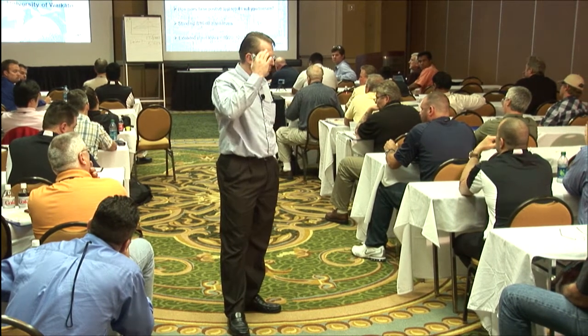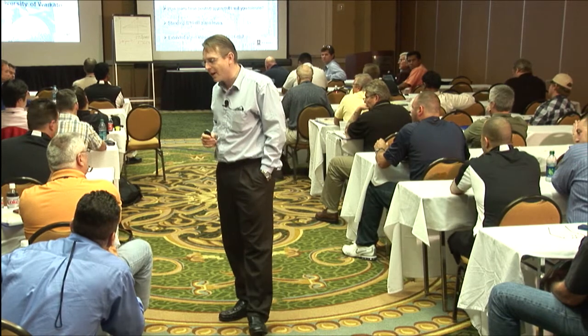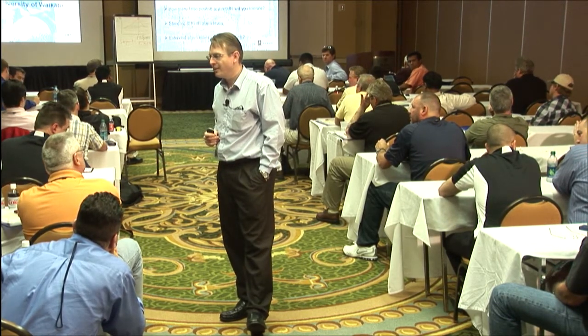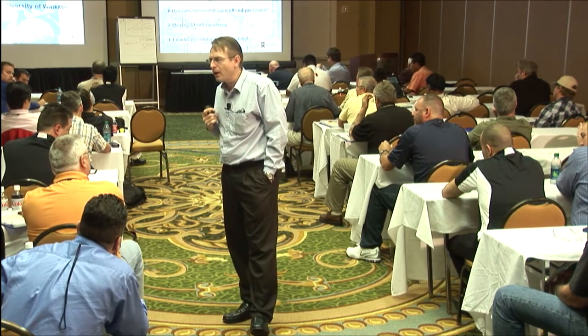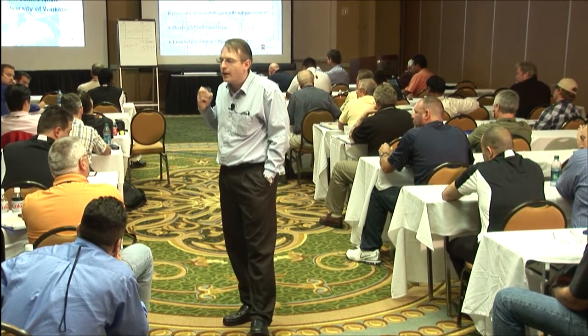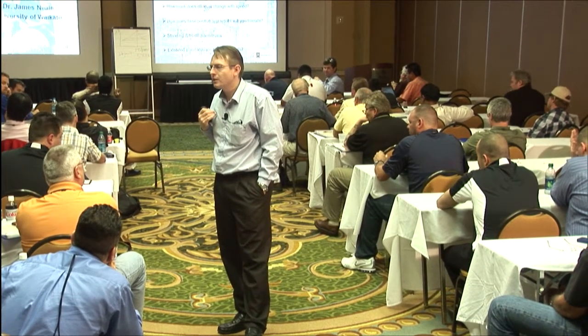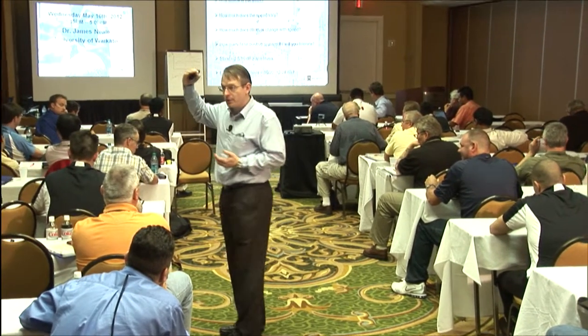Okay, your brain. Hopefully your brain. What's your brain connected to? Your ears. Okay, how can we use our ears? We're listening to that bearing, right? If the bearing's good, but just an elevated level because it's running faster, what's it going to sound like? It's going to be that same white noise, just at an elevated dB, right?